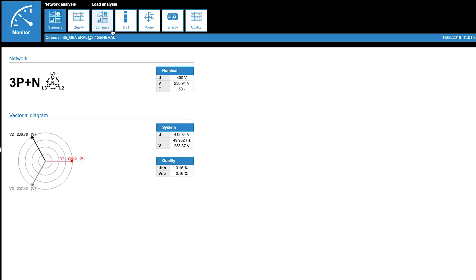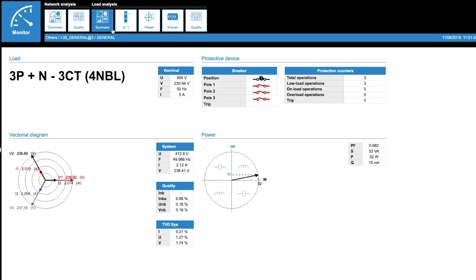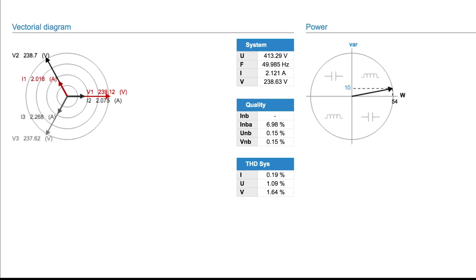By connecting to WebViewM, the web server embedded in the D70 display, the Fresnel diagram shows that some phase voltages and currents are out of phase. V1 is in phase with I2, while V2 is in phase with I1.